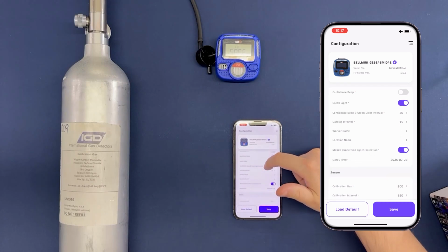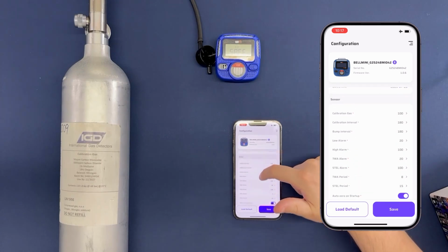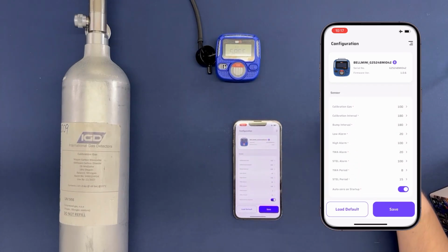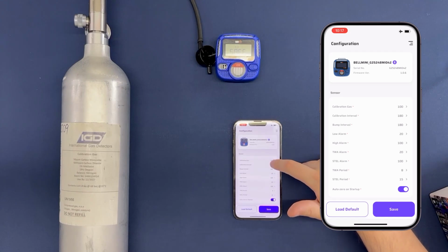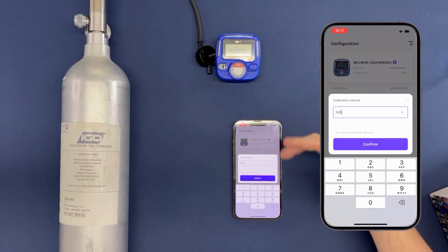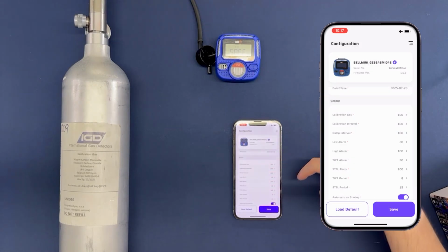Further down on the configuration side is the sensor specific settings. So with the toxic gases, it will have the calibration gas that you're using. You'll have the calibration interval and bump test intervals. And again, if you just click on one of these, it will have the days that you can set it from 0 to 365 days. As standard, these are the settings that arrive with your BELLMINI. It's set to 180 days for calibration interval, and all the alarm levels are set based on EH40 UK alarm levels.